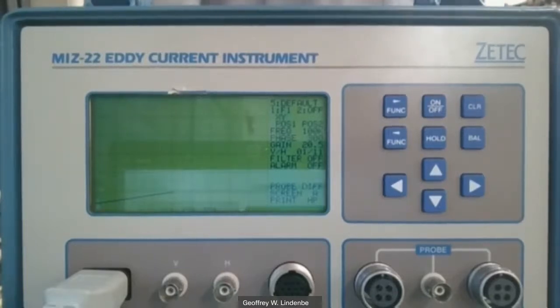The next one down is a filter. You can try playing with that if you want. The filter is designed to get rid of some of that extraneous, some of those extraneous indications caused by wobble or that kind of thing. But if you don't use it properly, it can also block a relevant signal. It's designed to block non-relevant or false signals, but if it's turned up too high, or tuned certain ways, it'll block your relevant signal.